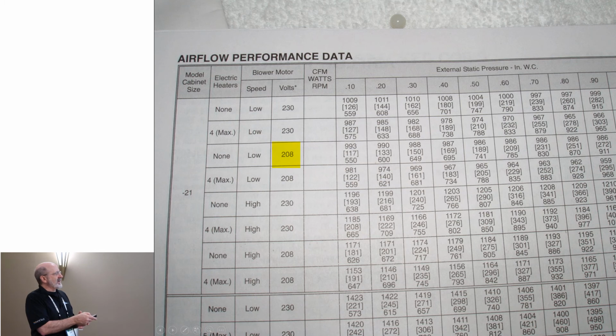The readings here are laid out a little differently: CFM, watts, and RPM. So CFM is 986, watts are 189, and RPM is 741. The interesting thing to notice here is, as you go across and range from 0.1 to 0.9 inches of water column, a full range of 0.8, the variation is almost nothing. It's 7 CFM. So this is an ECM motor.